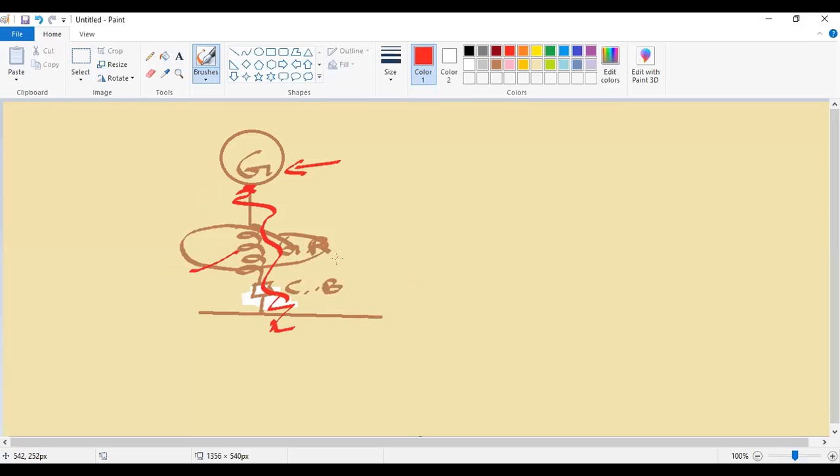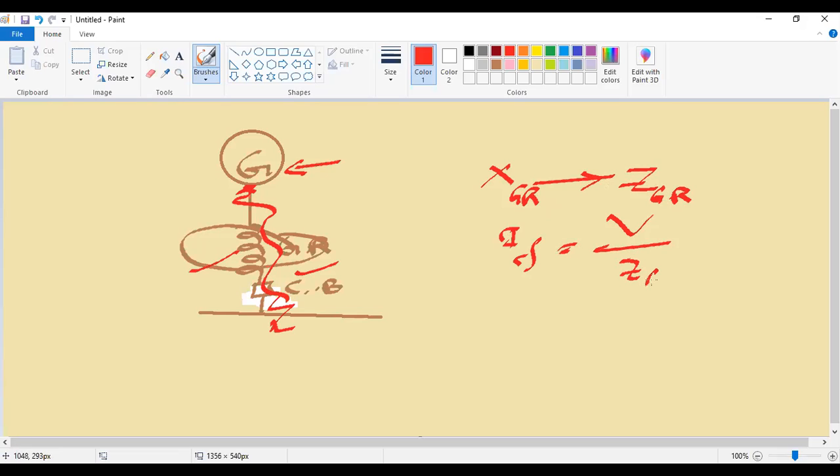So what we are doing actually, if we connect this generator reactor here, it will offer the inductance or the reactance, and when it is offering the reactance, finally it is offering the impedance of the circuit. So we know the fault current IF is basically V by ZR. So if this value is very, very high, this fault current will be low. So when this fault current is low, this generator will be affected by a lesser amount of current.